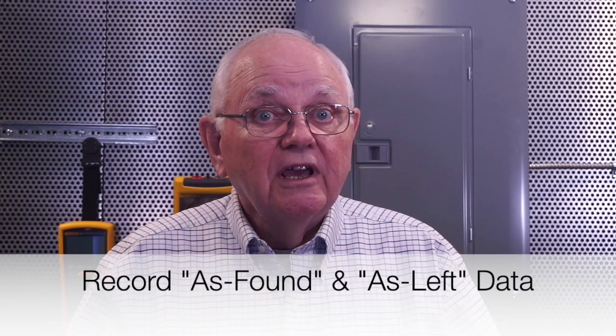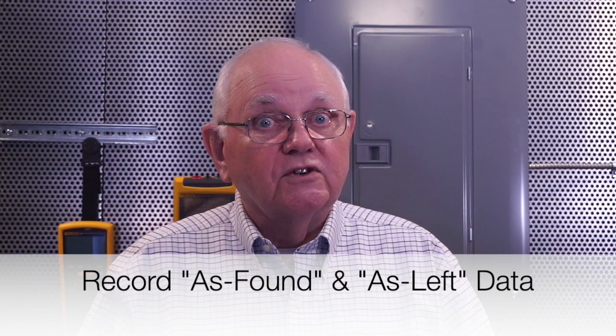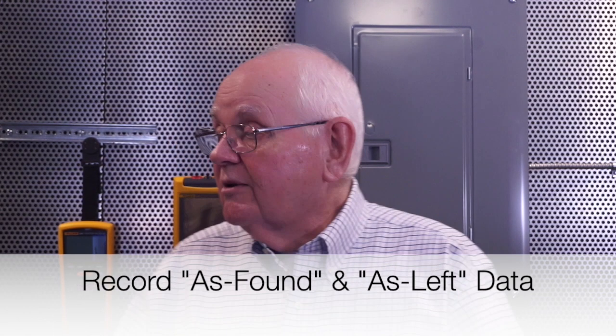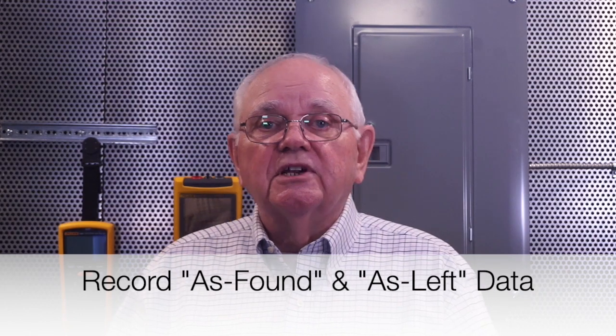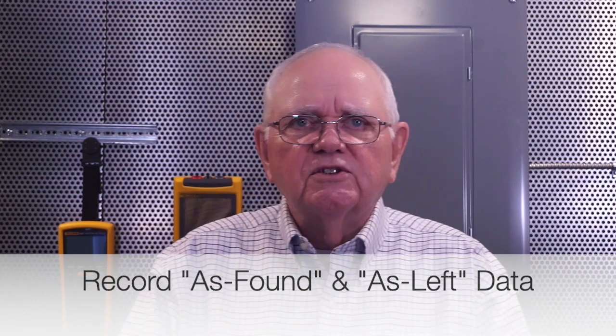Other tests you're probably familiar with are the as-found test and the as-left test we do on electrical equipment. So if I'm going to do an insulation resistance test on a motor, I want to know what the insulation resistance is when I first get there and check it, and record that data. Then, say I had to dry the motor out, what does my as-left data look like?